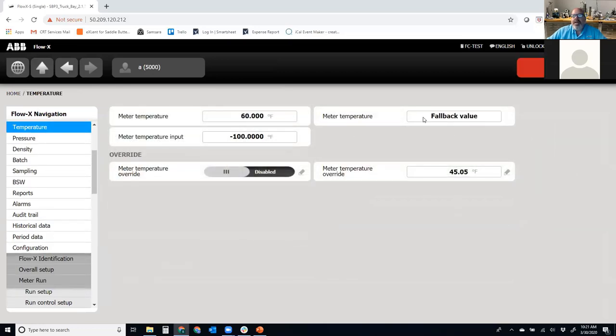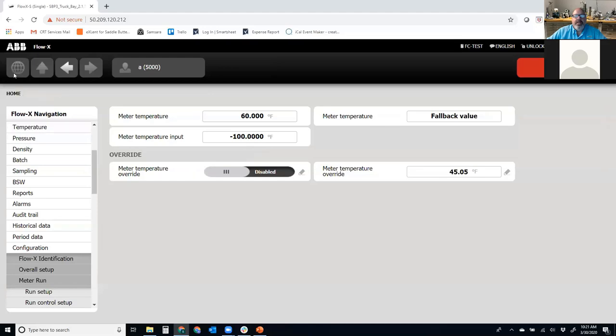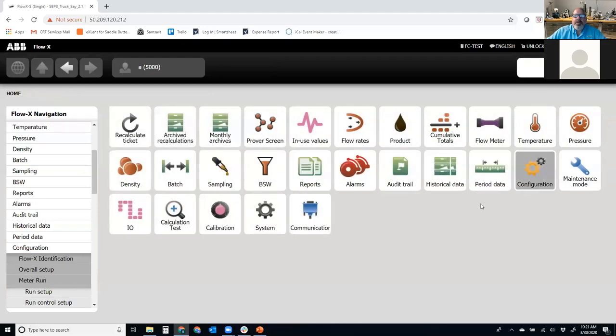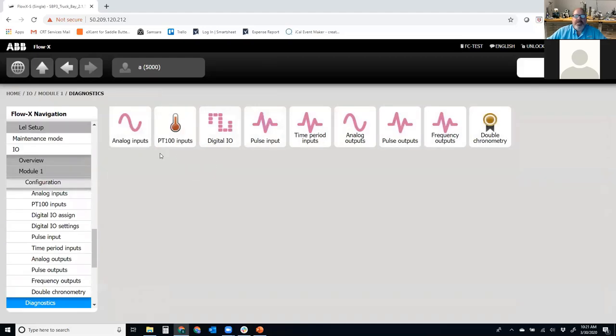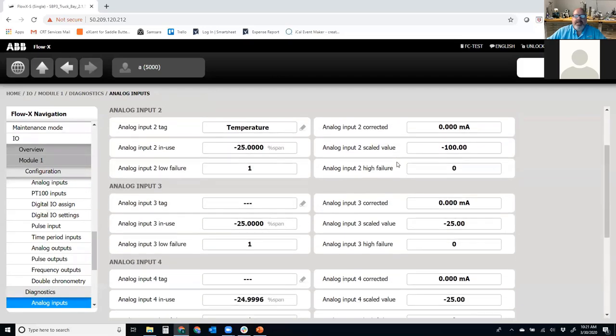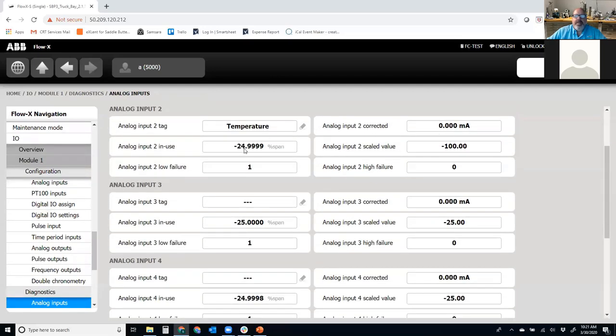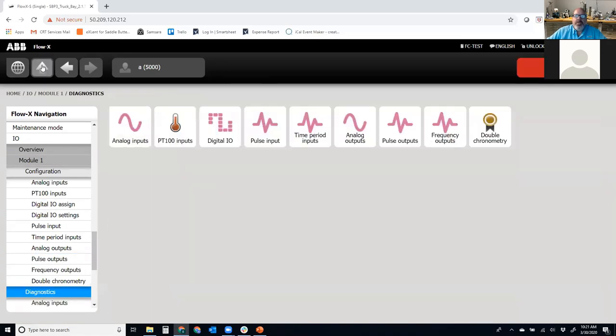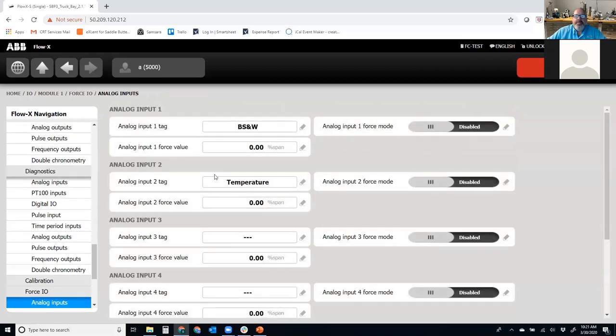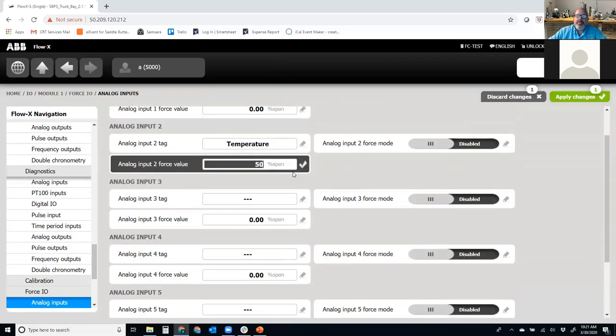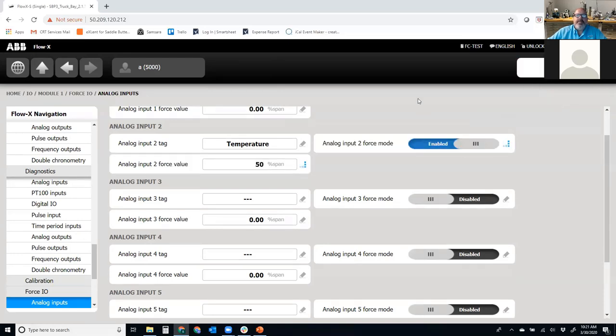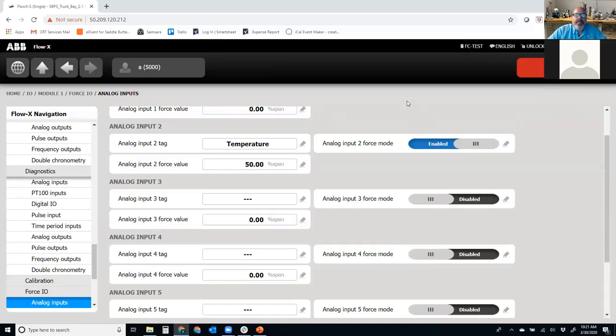And I need to tell it, for temperature, look at your analog input, go to your module, go to analog input number two, and it'll come up as temperature. And then I'll read what the temperature is. In this case, it's going to be nothing because I don't have an analog input put into it. But if I was to force that real quick. Right now, it's at a fallback value of 45.05. And you can see my temperature is fluctuating.